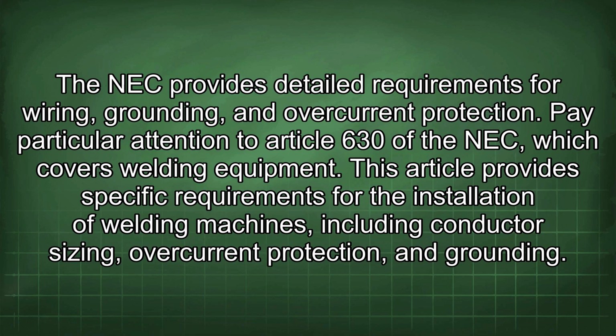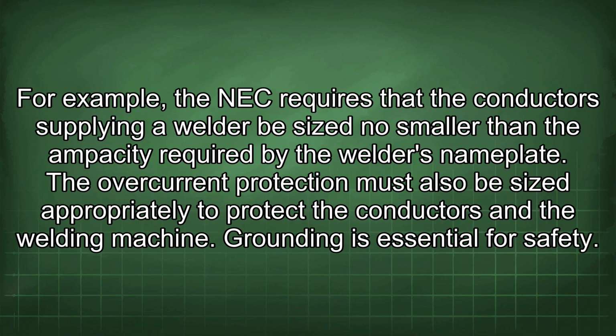The NEC provides detailed requirements for wiring, grounding, and overcurrent protection. Pay particular attention to Article 630 of the NEC, which covers welding equipment. This article provides specific requirements for the installation of welding machines, including conductor sizing, overcurrent protection, and grounding. For example, the NEC requires that the conductor supplying a welder be sized no smaller than the ampacity required by the welder's nameplate. The overcurrent protection must also be sized appropriately to protect the conductors and the welding machine.